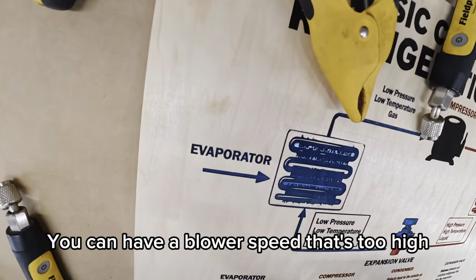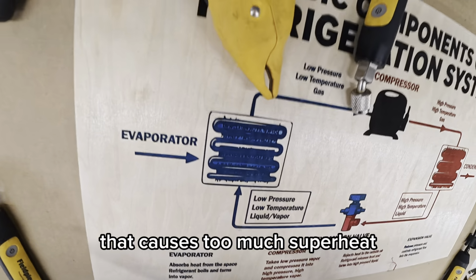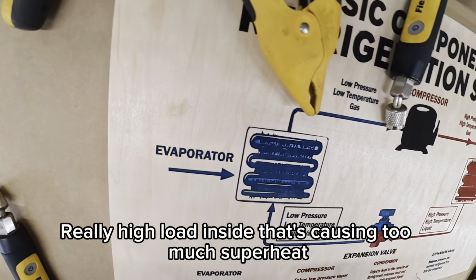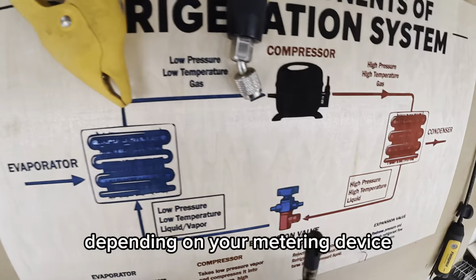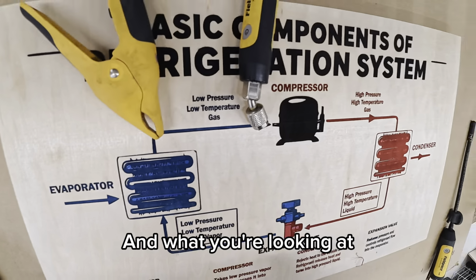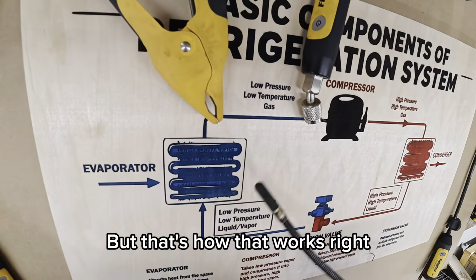You can have a blower speed that's too high that causes too much superheat. You can have a really high load inside that's causing too much superheat, depending on your metering device and what you're looking at. So many different scenarios, guys. That's how that works, right?